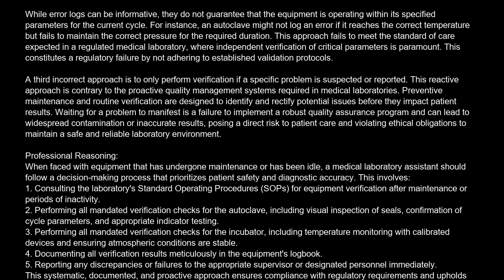When faced with equipment that has undergone maintenance or has been idle, medical laboratory assistants should follow a decision-making process that prioritizes patient safety and diagnostic accuracy. This involves: 1. Consulting the laboratory's standard operating procedures, SOP, for equipment verification after maintenance or periods of inactivity. 2. Performing all mandated verification checks for the autoclave, including visual inspection of seals, confirmation of cycle parameters, and appropriate indicator testing. 3. Performing all mandated verification checks for the incubator, including temperature monitoring with calibrated devices and ensuring atmospheric conditions are stable. 4. Documenting all verification results meticulously in the equipment's logbook. 5. Reporting any discrepancies or failures to the appropriate supervisor or designated personnel immediately. This systematic, documented, and proactive approach ensures compliance with regulatory requirements and upholds the highest ethical standards for patient care.